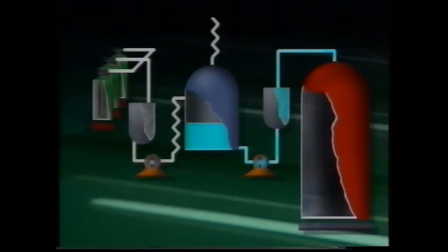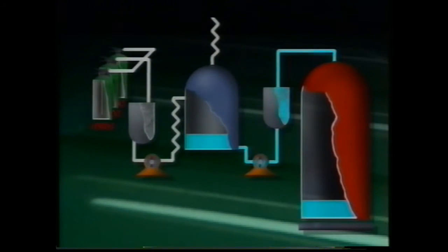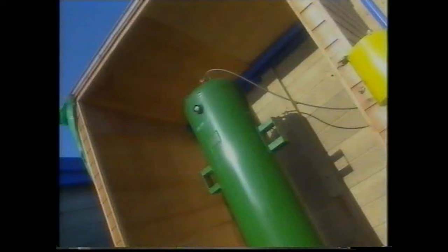At this stage, the halon is passed through the first of two highly efficient filter processes. Nitrogen, used for pressurizing extinguishers, is then separated from the halon before being released harmlessly into the atmosphere. On its journey from the holding tank inside the unit, the halon is subject to further filtration. Here, it passes through dedicated filters which remove any remaining traces of moisture, together with trace elements like oils, acids, or contaminant particles deposited from inside the extinguisher body. Filtration complete, the reclaimed halon is then pumped into a high-capacity external tank for weight-tested bonded storage.